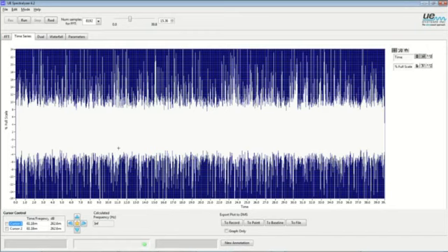And the other thing that's noteworthy on these discharges is they are not uniform or linear in amplitude. And that's an important thing. What that tells us, the nonlinearity, says the intensity of the discharge is varying. So it's changing throughout the recording. It is not the same, and that's important to understand.